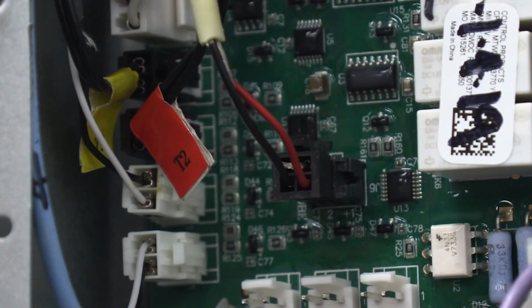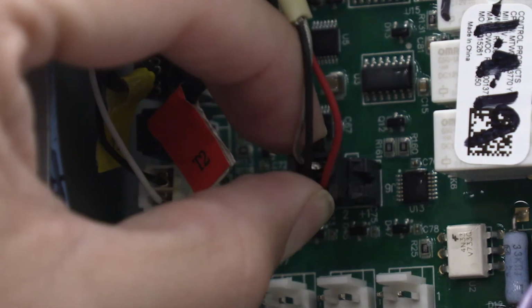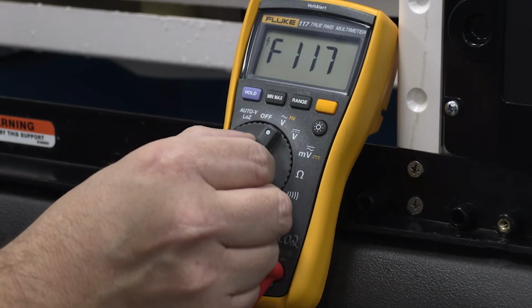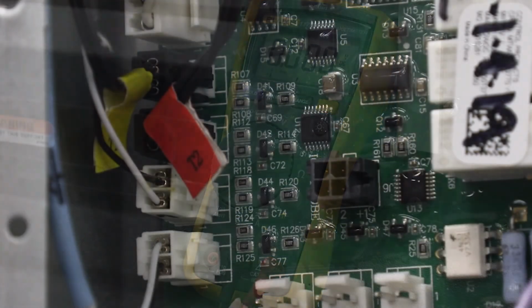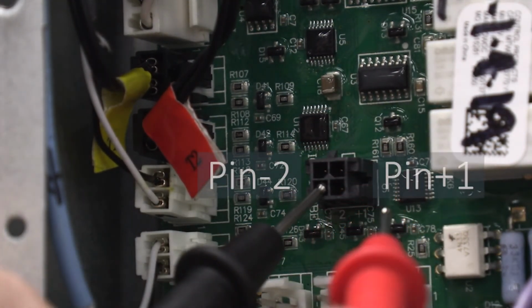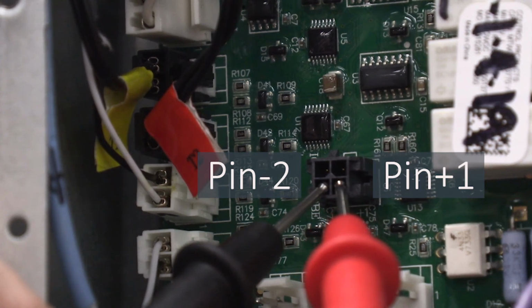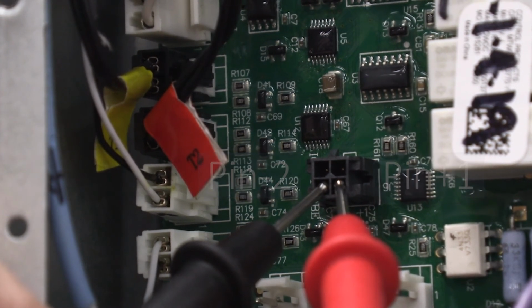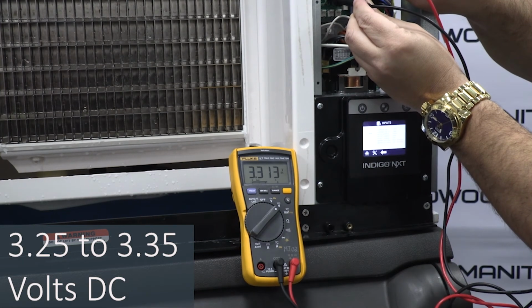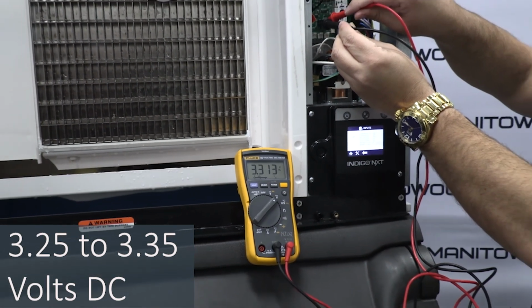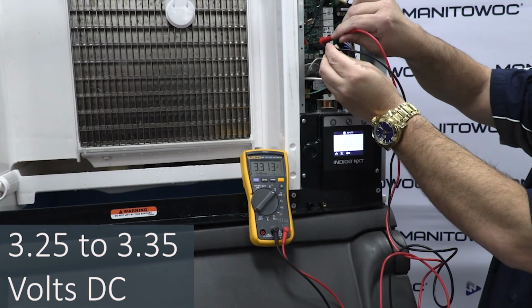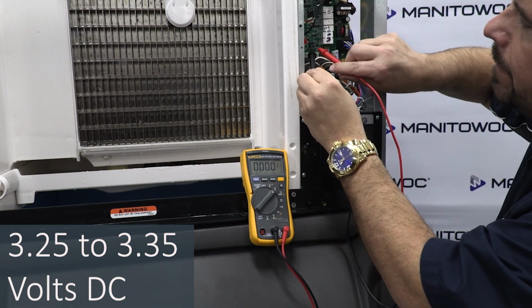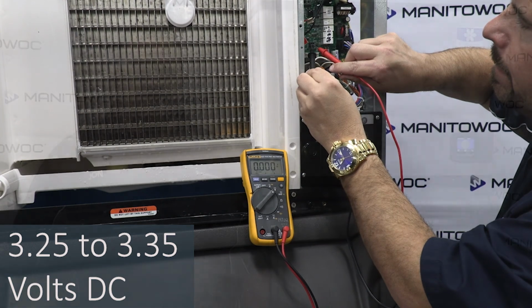Step 10. Next, we're going to check the control board for the correct output voltage. Unplug the ITP and set a voltmeter to the DC voltage scale. Then, measure voltage across pin 1, positive, with the red lead, and pin 2, negative, with the black lead. If the voltage measures 3.25 to 3.35 volts DC, the control board is functioning correctly and the problem is with the ITP. If the voltage does not measure between 3.25 and 3.35, replace the control board.